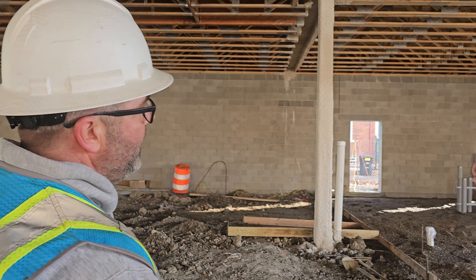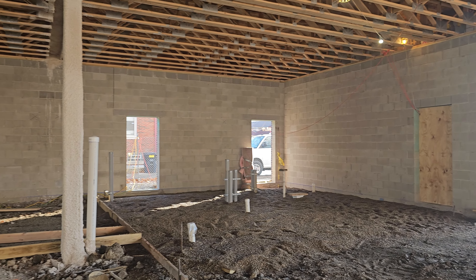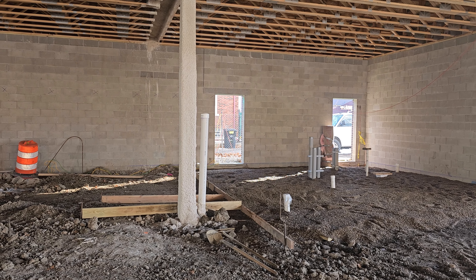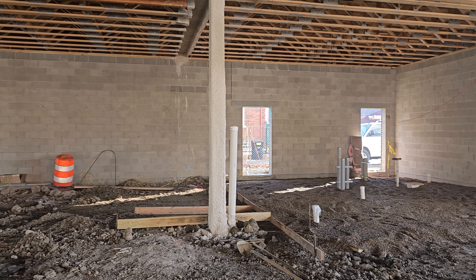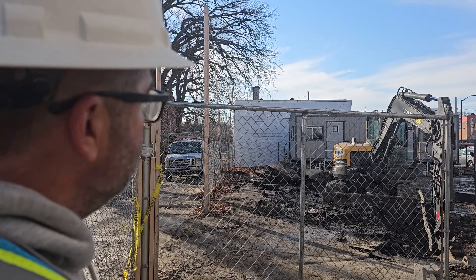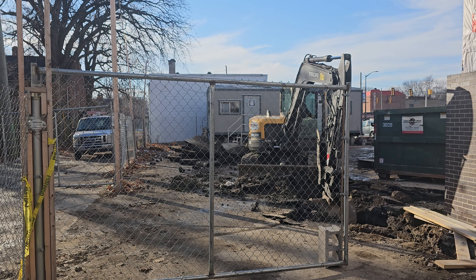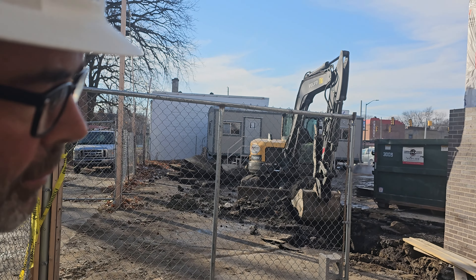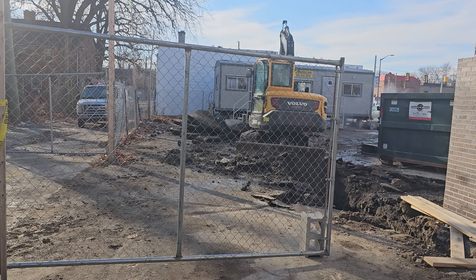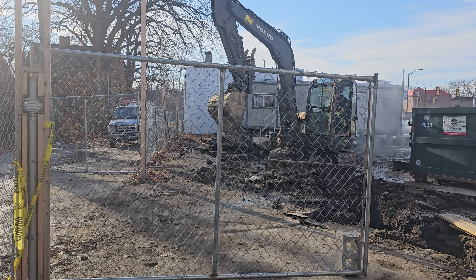This is the utility room — it's where the elevator, electrical maintenance closets, water mains, and fire suppression all come back to. We need to have this slab poured so we're able to get everything required in that room, and we'll pour that now to keep the job rolling. Buck Construction is digging our power lines back for DTE. We're opening this trench up — the electricians will put their pipes, we'll get it inspected, then backfilled. We've got three five-inch pipes roughly that go to the alley, and DTE picks it up from the alley underground.